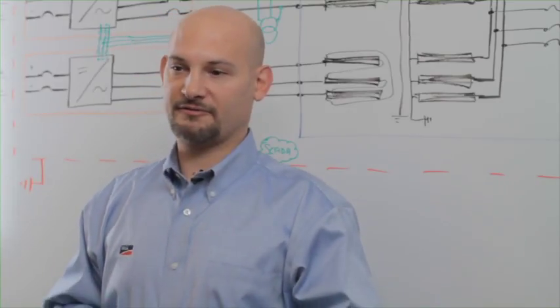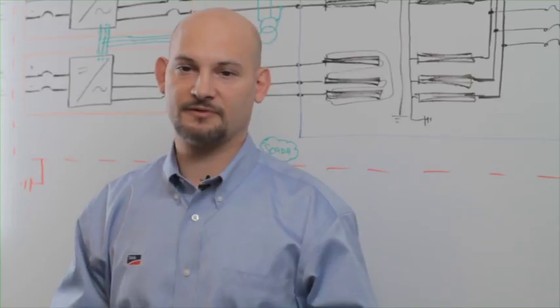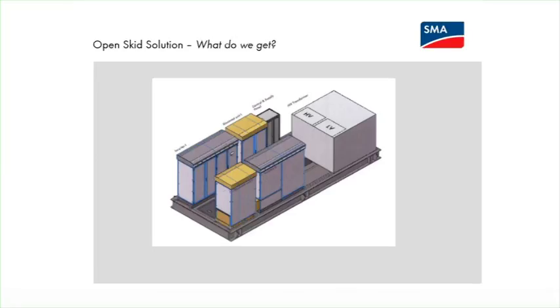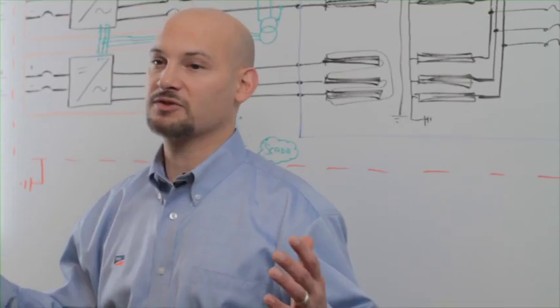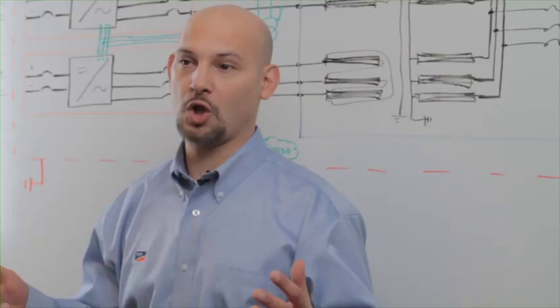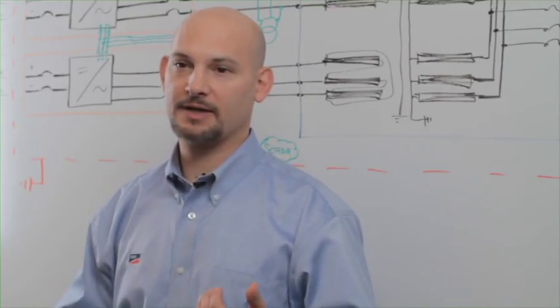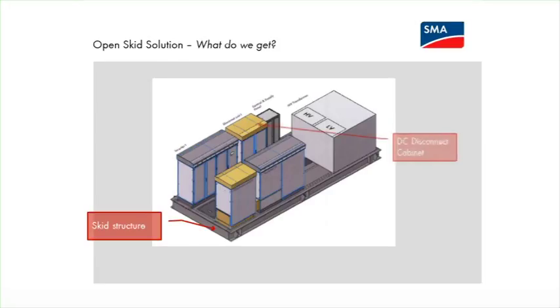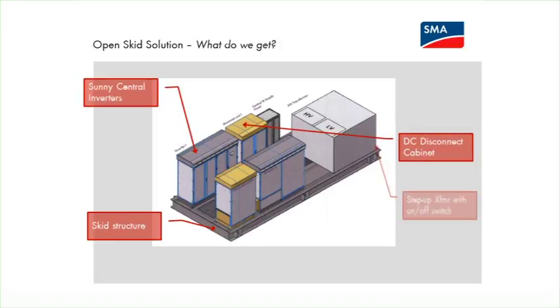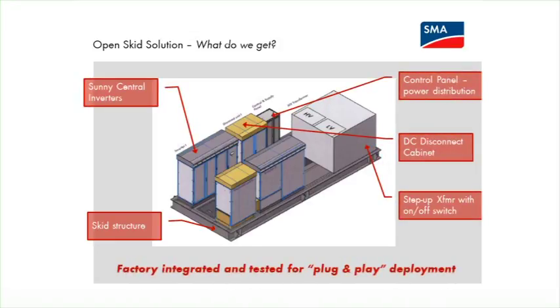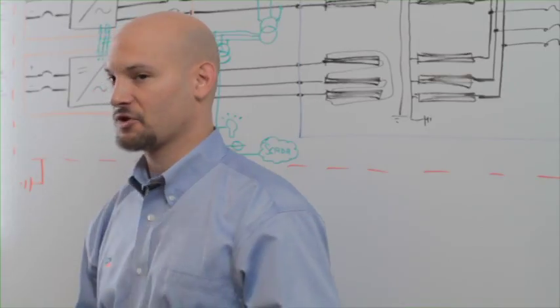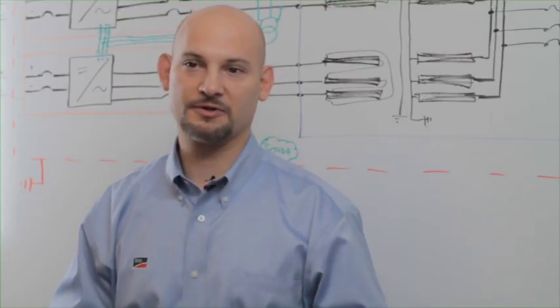So in terms of standard equipment versus optional equipment, the standard deliverable would include the skid itself, and that's a steel structure. To give you a feel for scale, it's roughly 12 foot wide by 30 foot long. The steel structure then has dropped on it the DC disconnects, the inverters, the control power and station power transformers, and the medium voltage transformer and switchgear. So all of this is factory assembled, delivered turnkey to your site.